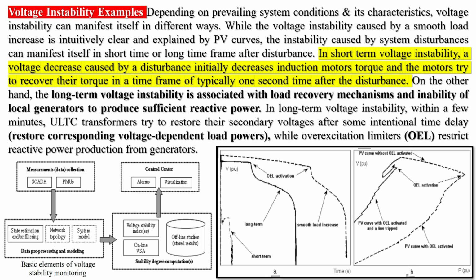On the other hand, the long-term voltage instability is associated with load recovery mechanisms and inability of local generators to produce sufficient reactive power. In long-term voltage instability, within a few minutes, ULTC transformers try to restore their secondary voltages after some intentional time delay, restoring corresponding voltage-dependent load powers, while overexcitation limiters, OEL, restrict reactive power production from generators.